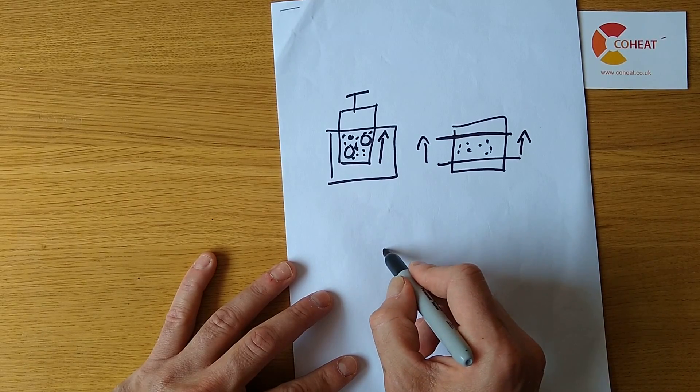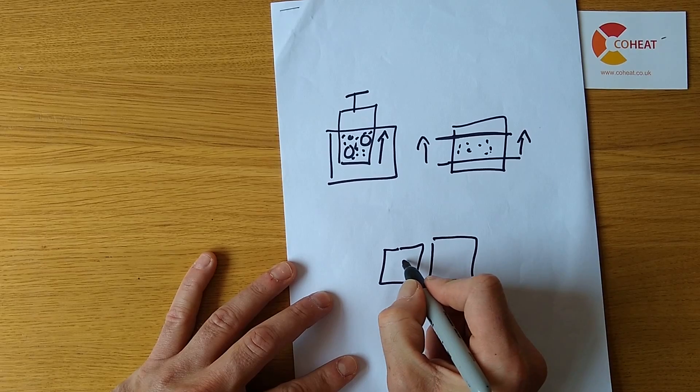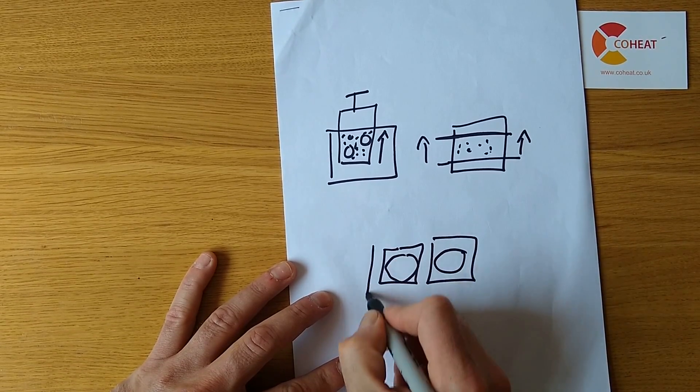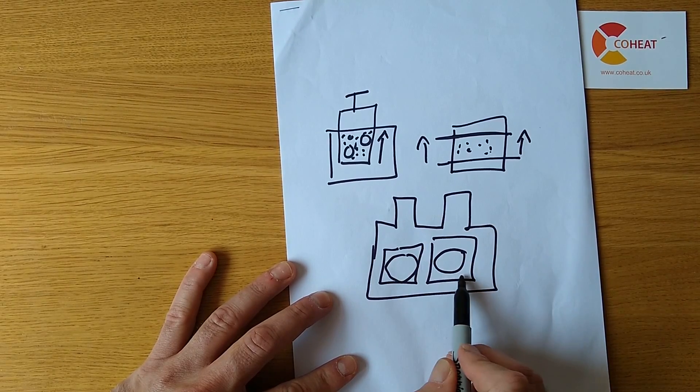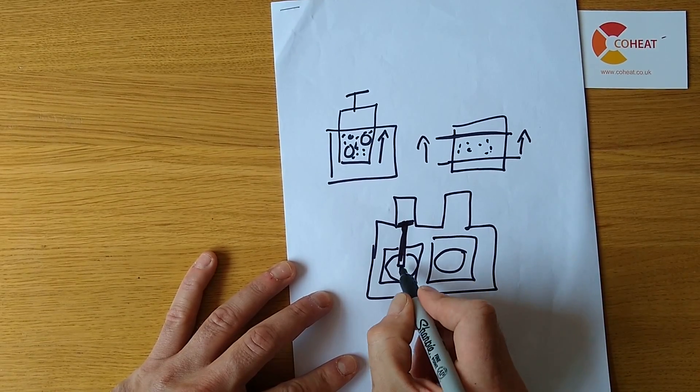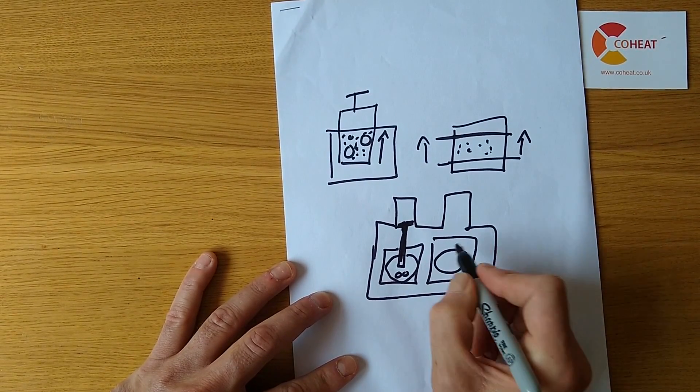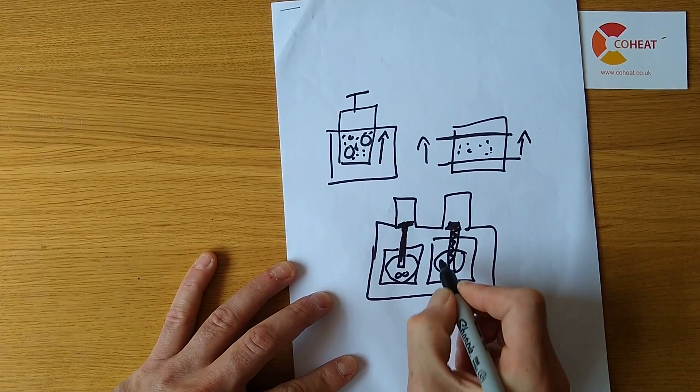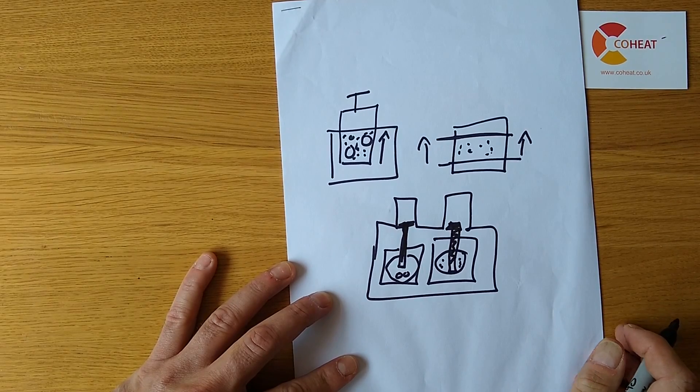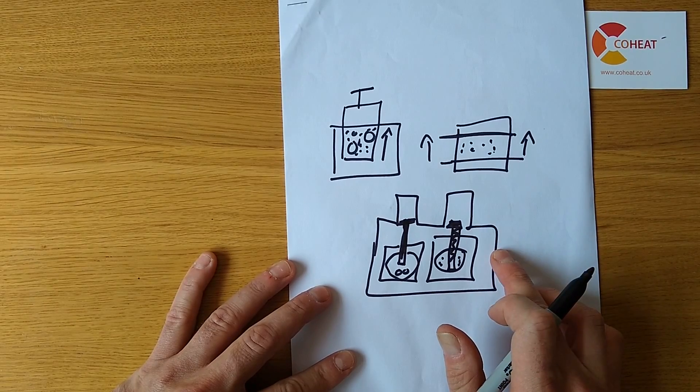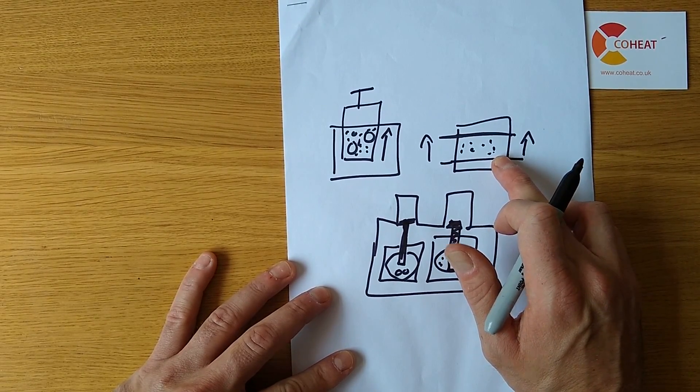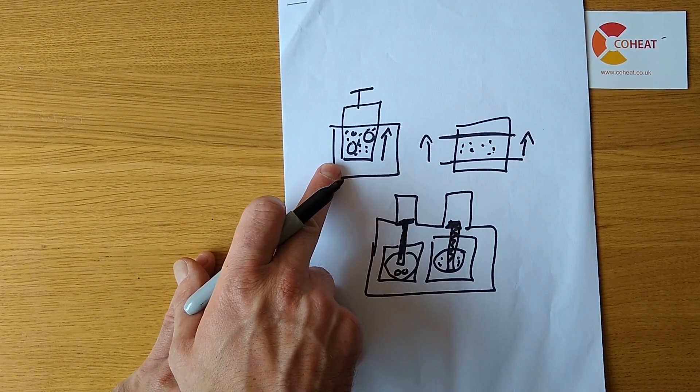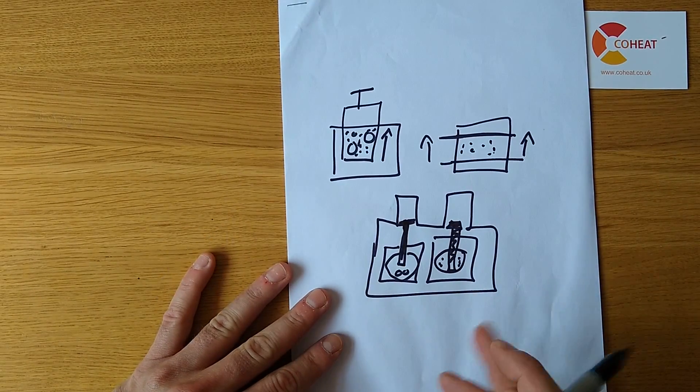Often you see cheap and cheerful Wicks, Screwfix style chocolate boxes, which have their two metal terminal blocks inside, with a screw that hopefully traps both of your cables underneath at the bottom there, but often in practice completely misses your cable and has them scattered around the side. This style of chocolate box should never be used on an MBUS network in my opinion. It's asking for trouble. These Wago 221s cost about 50p per connection. These style of terminal blocks you'll find on all expensive equipment, be it BMSs or heat meters, and it's there for a reason. It's to make sure you have a decent connection.